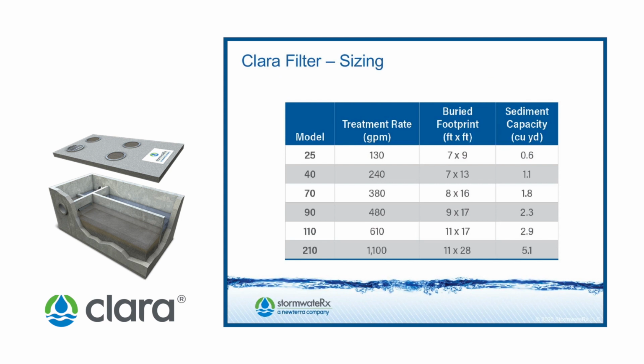Clara filter sizing. The basis for sizing the Clara filter is strictly flow-based. This table depicts the model number associated with each treatment flow rate. Again, I want to emphasize that the flow rate shown in this table is the offline water quality flow rate, not the peak flows. Please make note of this important value when choosing a Clara filter size.